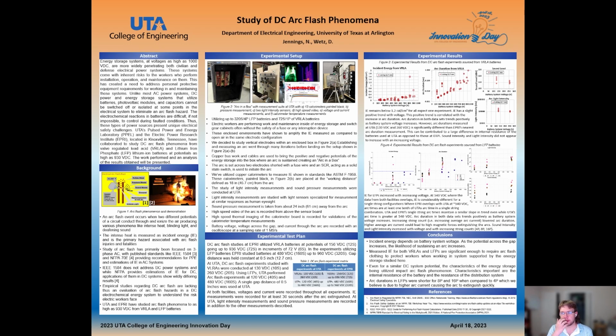And more importantly, I think one big discussion from this is the topic about the difference between and characteristics of individual energy storage. So, for example, at the same DC potential shown between the LFPs and VRLAs, we saw much different incident energy and arc flash light and sound produced. As a result, it's pretty important to, as a part of future DC models, include these in calculations and understandings of how to go forward and estimate incident energy. Finally, the arc durations in LFPs were shorter for the 8P and 16P strings when compared to the single 4P string, which we believe is due to the higher arc current causing the arc to extinguish quickly.